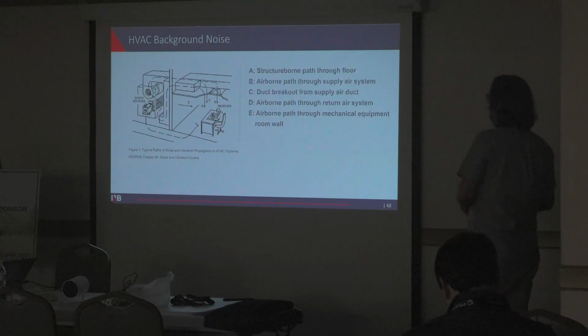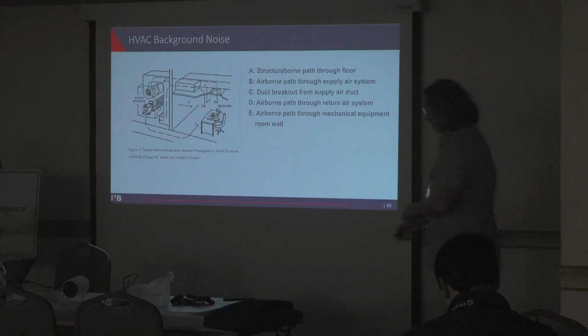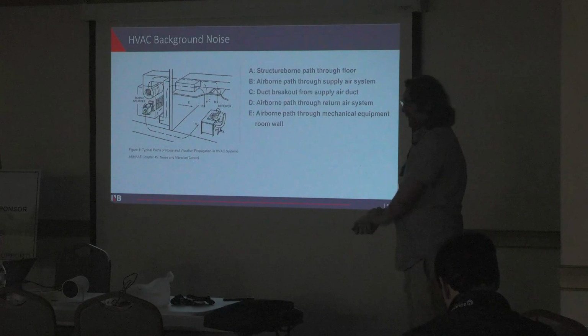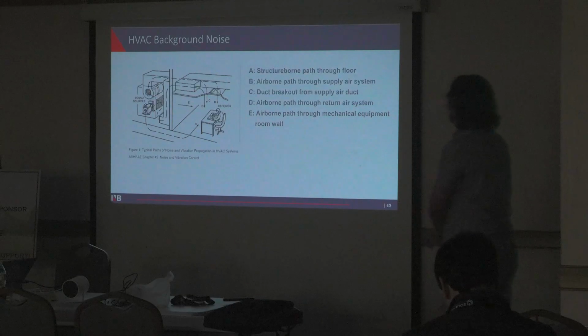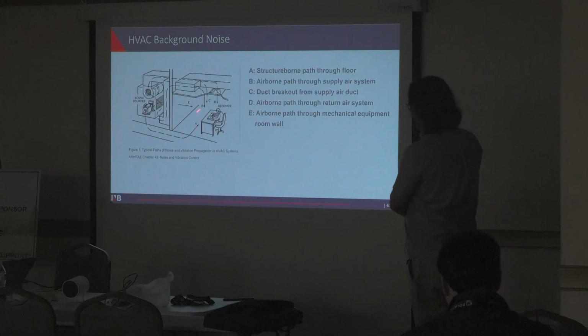So what are the paths we look at for HVAC background noise? ASHRAE also lists a group of paths, we refer to them as the ASHRAE paths. These list 5 of them. There's actually 8 in total, but these are the most common that we look at. So when we look at HVAC background noise for a space, we'll take, say, a typical private office.